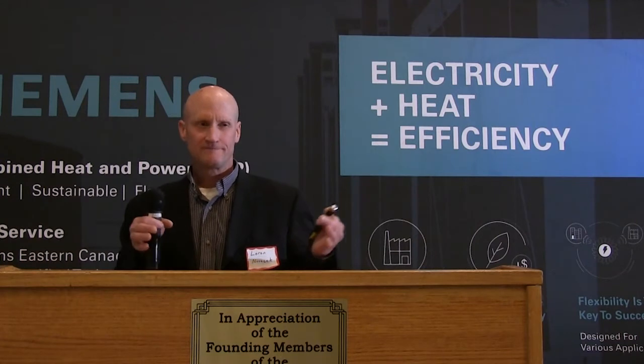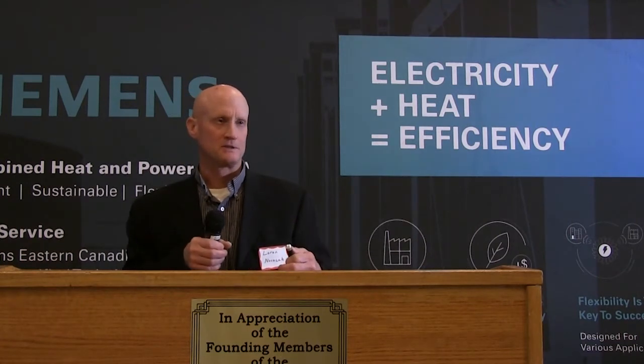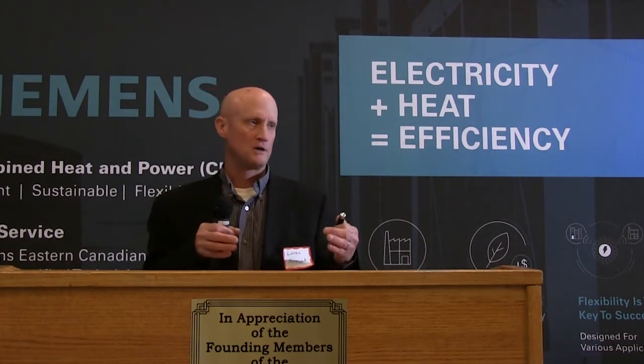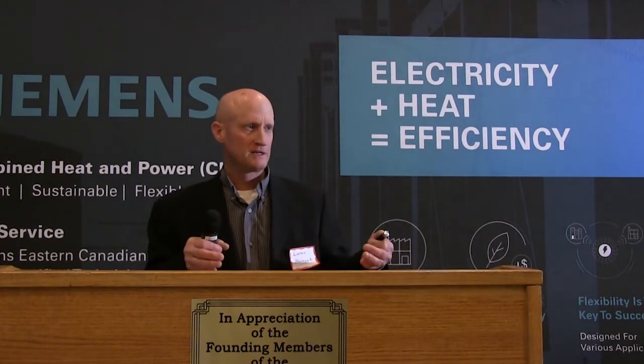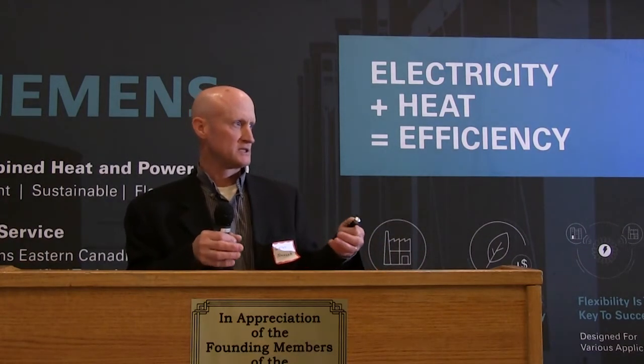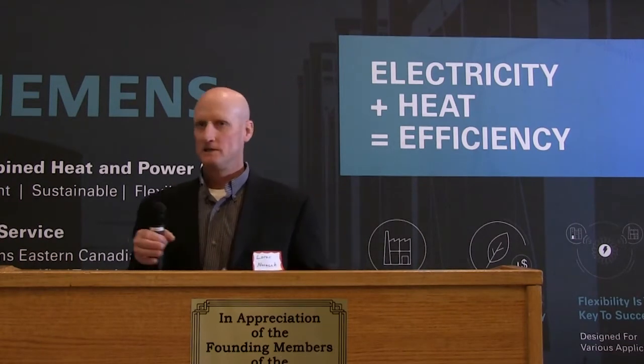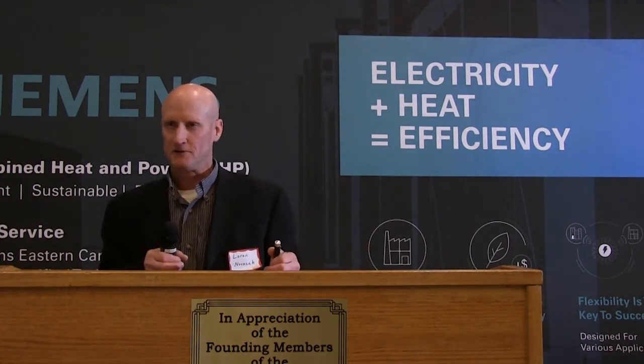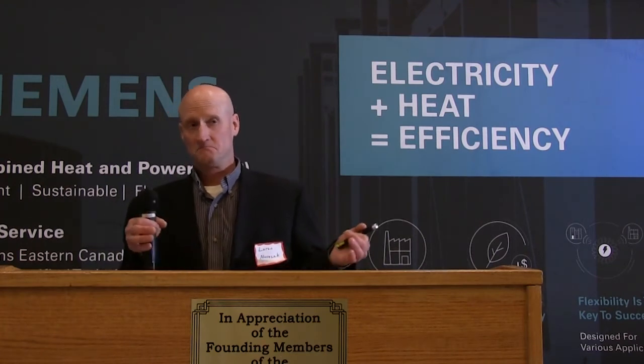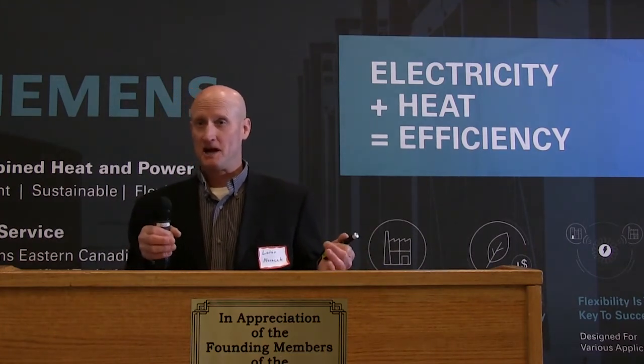Typical working life varies—every application is a little bit different. We always size it for the project; we try to stay away from a standard size and instead fit the SCR system to that particular application. But nominally, we'd say 16,000 hours. What does that mean? Well, there's almost 8,760 hours in a year, so that means there's about 2 years of life in that catalyst.